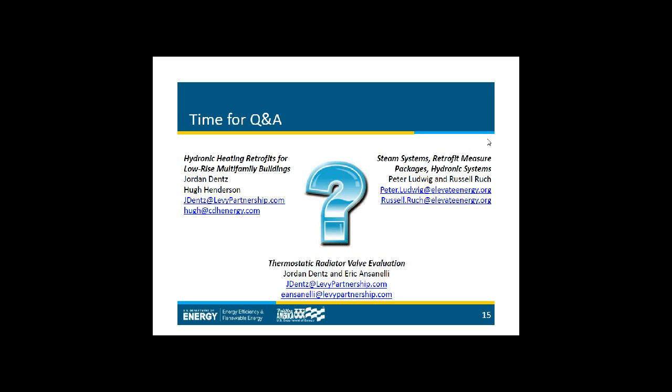Yeah, so this is Hugh. I guess I'll take that one. So we did try a 10-degree setback for a while. So we did try a bigger setback, and we were concerned there were some tenants in that building that worked the night shift, or had an offset schedule, so they were up at night. And we had a little bit of feedback that there might have been a problem, so that's why we backed off on that.